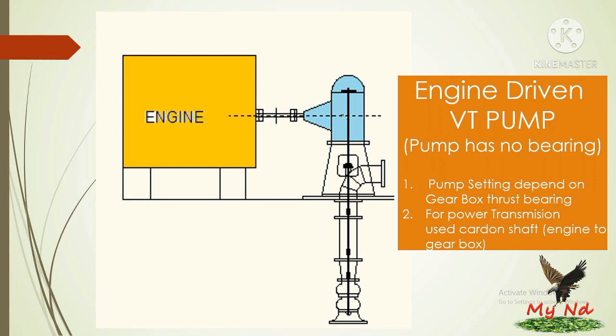Another example is the engine driven VT pump. In that type, the pump has no bearing. Pump setting depends on the gearbox thrust bearing. For power transmission, a Cardan shaft is used from engine to gearbox. In that type, a 90-degree gearbox is used for power transmission.